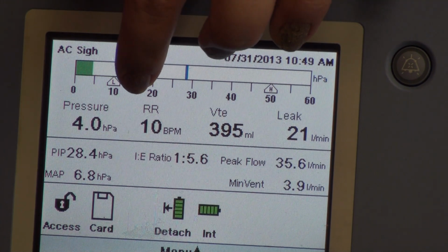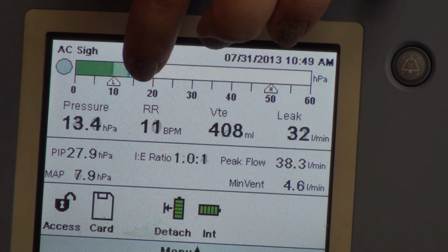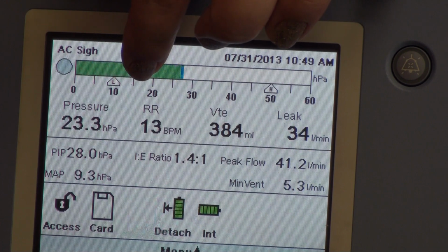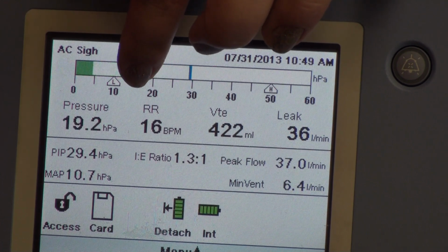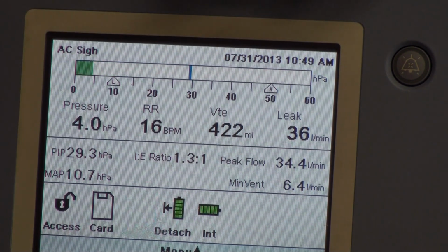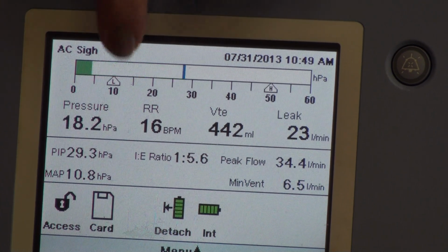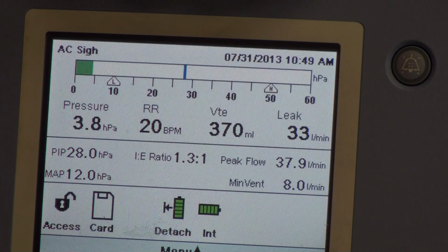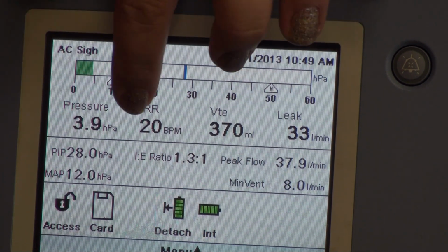So this says 10 here right now, and if I had some client breaths on my own here, it's up to 13, but what if that's auto cycling? Now it says 16. Well, I didn't press it that many times and it caused 16 breaths. It's an average. That's why we time our clients. Now it's up to 20, say I did 20 breaths per minute.